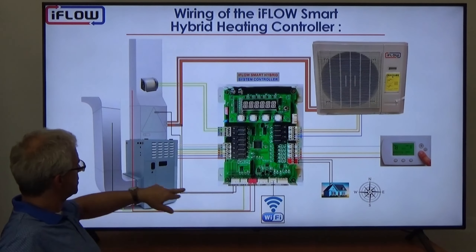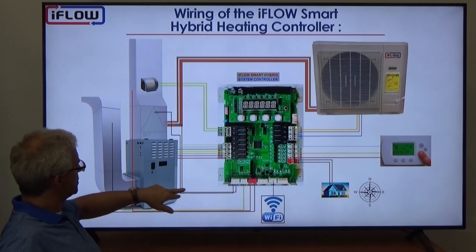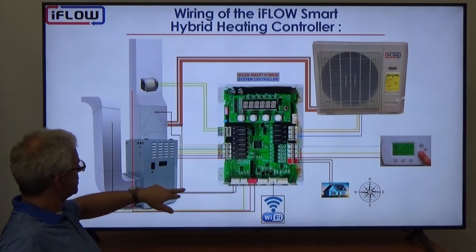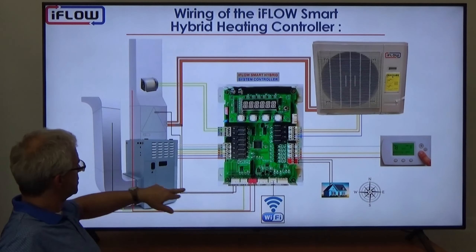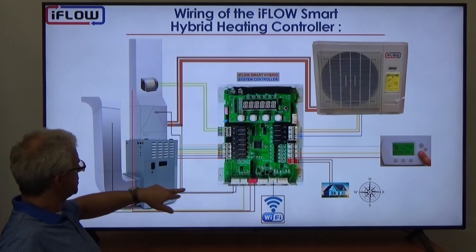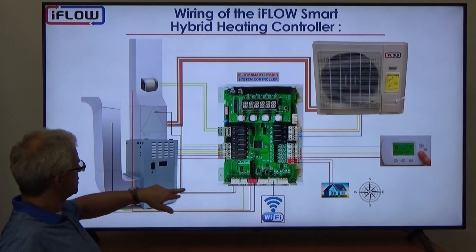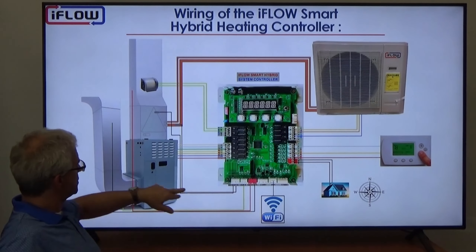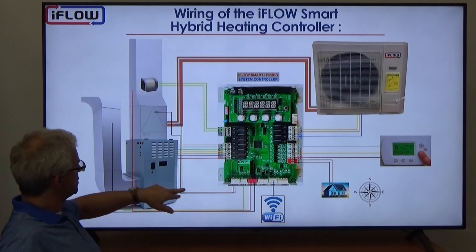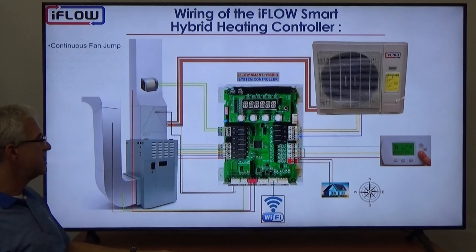All of this is in the smart switching controller — capabilities that thermostats would never have. We use any thermostat, no heat pump thermostat required, and only need three wires minimum: R, W, and Y — three wires in, three wires out. Contractors sometimes call saying they only have three or four wires in the wall, but with iFLOW that's perfectly fine. Just bring those in, tell us when there's a call for heating or cooling, and we'll take care of the rest.